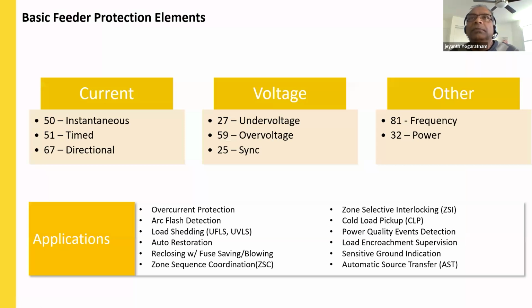Let's look at the feeder. What is a feeder? Feeders are the conductors and cables connecting the distribution substation to the primary circuits or to the load. When it comes to the basic feeder protection, the main current-related protections are the 50-51 function, where 50 is the instantaneous overcurrent element and 51 is the time inverse overcurrent element. However, there are other protection functions which work on the current signals as well as the voltage signals as shown in this diagram. The voltage protection elements are under voltage, over voltage, and the synchro check functions, and the power and the frequency elements work with voltage and current signals.